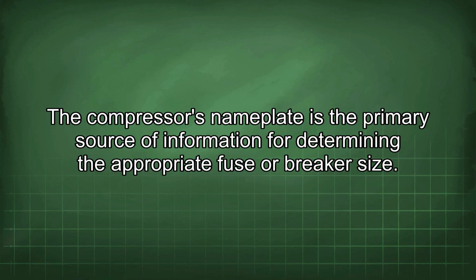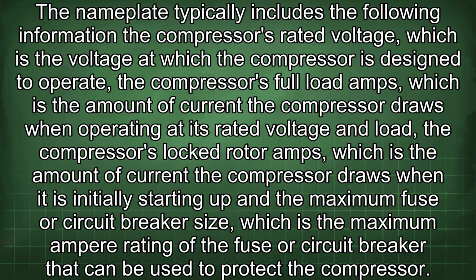The compressor's nameplate is the primary source of information for determining the appropriate fuse or breaker size. The nameplate typically includes the following information: the compressor's rated voltage, which is the voltage at which the compressor is designed to operate; the compressor's full load amps, which is the amount of current the compressor draws when operating at its rated voltage and load; the compressor's locked rotor amps, which is the amount of current the compressor draws when it is initially starting up; and the maximum fuse or circuit breaker size, which is the maximum ampere rating of the fuse or circuit breaker that can be used to protect the compressor.